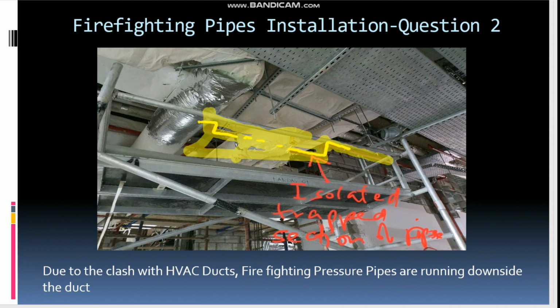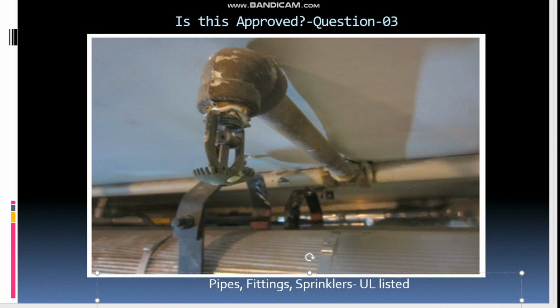So is this arrangement acceptable? That's the first question. And secondly, if this is not approved, then what is the alternate arrangement you have to propose? And if you propose that alternate arrangement, how to calculate the water volume or something else? Let's discuss that in the second part with the proper backup. Coming to the third question, here we have the pipes, fittings and sprinklers. All these materials are approved. We have proper material submittal approval also. My question is, there is an issue in the installation. If you already found the answer, don't forget to press like.